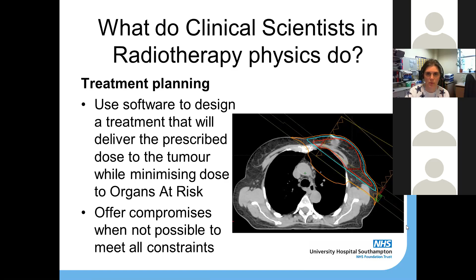We also do quality assurance, as many of my colleagues have already mentioned. A lot of it is checking that equipment is working as it should be, because with radiation and other modalities, the outcome, if your equipment's not working properly, can be very serious. So a lot of the QA checks within radiotherapy are making sure that our linear accelerators are working within specifications and that their performance continues to match the beam model that has been used in the treatment planning software. As long as these match, that will make sure that the treatment that we plan in the software will match the treatment delivered by the LINAC.